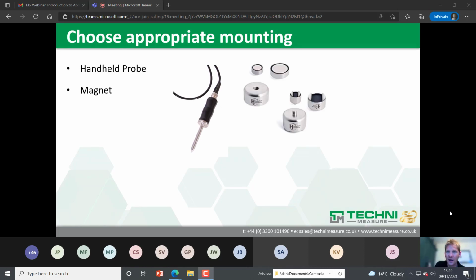I'm going to quickly recap the mounting considerations. Keith's already covered this, so I'm going to whip through it. There are various types you can get, from the very simple handheld probe, to magnet mounts, either a flat single pole magnet or dual pole magnets, which can be used for circular or uneven surfaces. Then adhesive mount accelerometers, where you literally glue or bond the accelerometer onto the structure, typically using cyanoacrylate adhesive or epoxy adhesive. Again, make sure you choose an adhesive that's going to withstand the environment. If it's a hot environment, it needs to be a high temperature adhesive. If it's going to be a longer term measurement, make sure you have an adhesive that will last.